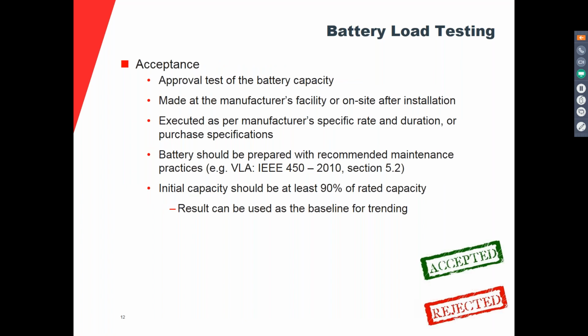So the acceptance test is an approval test of the battery capacity. It can be performed at the manufacturer facility or on site right after the installation. Usually it is performed in the very first 6 months, once the battery has been delivered and installed and has been under floating conditions for a while. So the battery capacity has developed fully, and that is when the test is performed, to accept and also to get a benchmark value. You want to know what capacity the battery is starting with.